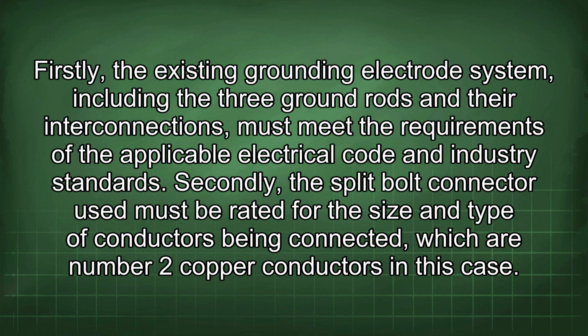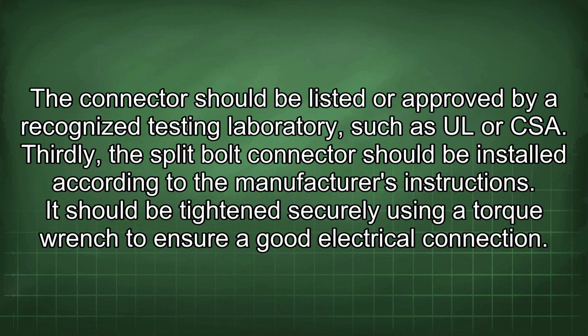Secondly, the split bolt connector used must be rated for the size and type of conductors being connected, which are number 2 copper conductors in this case. The connector should be listed or approved by a recognized testing laboratory such as UL or CSA. Thirdly, the split bolt connector should be installed according to the manufacturer's instructions. It should be tightened securely using a torque wrench to ensure good electrical connection.